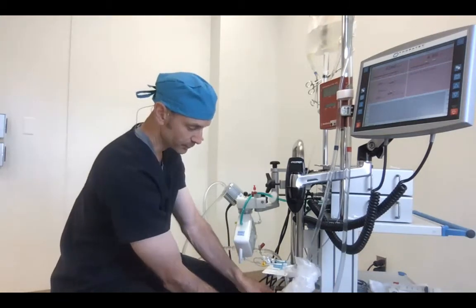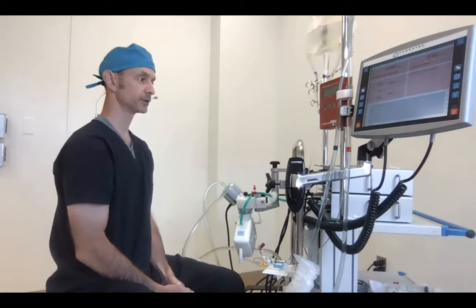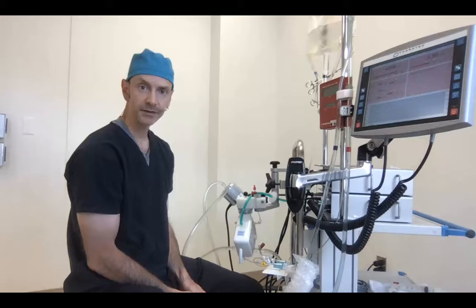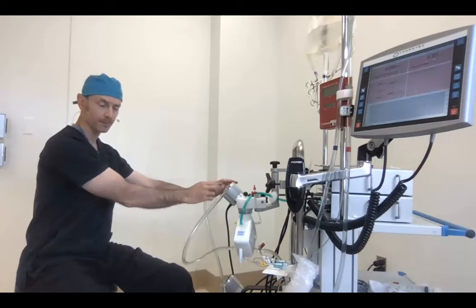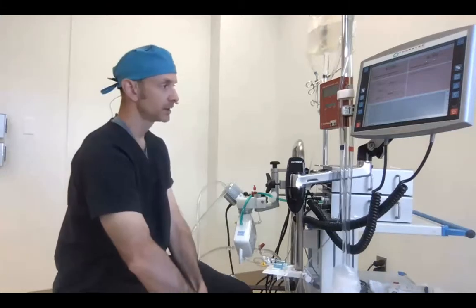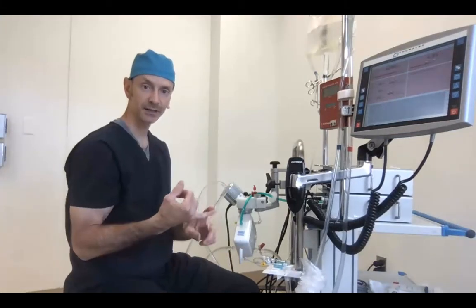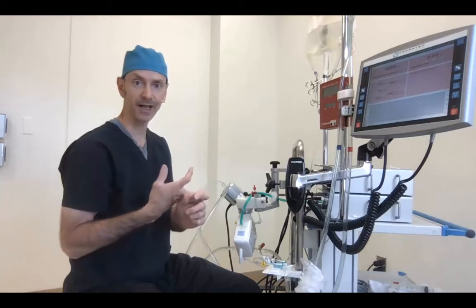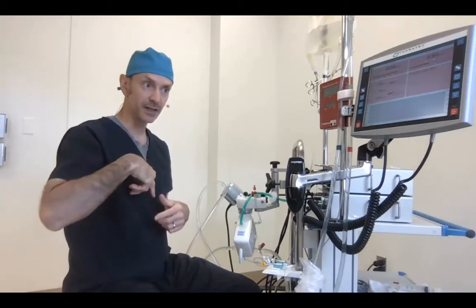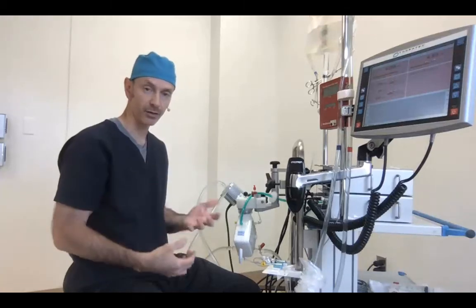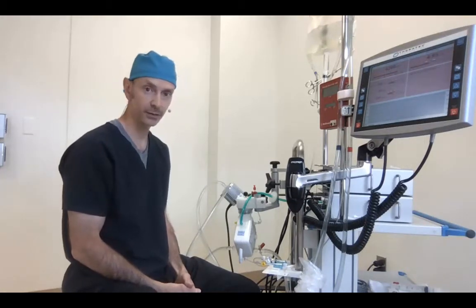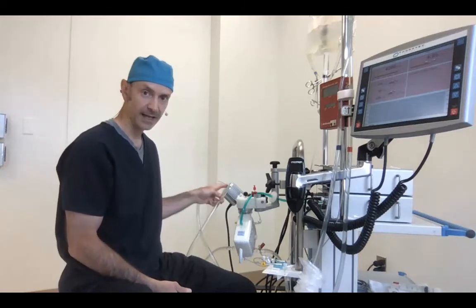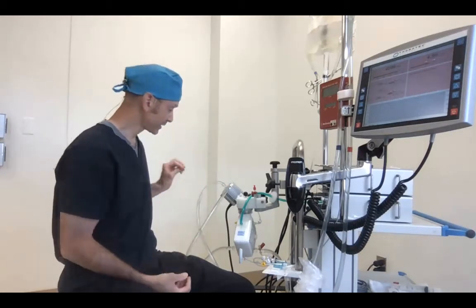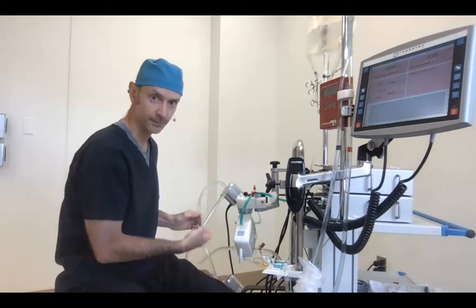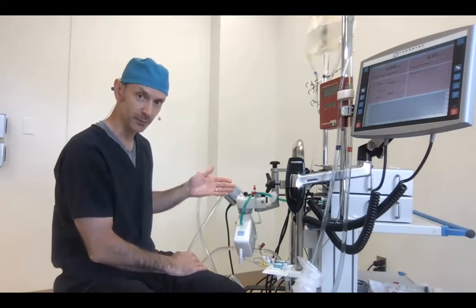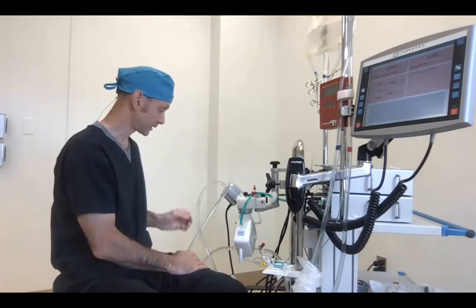But we're doing a demonstration of preload and afterload resistances. So what's preload? Preload is everything before this pump. So here's our pump, and this whole venous line up to the patient, the size of the cannula, the position of the cannula, the volume status of the patient, the position of the cannula inside the patient, the position of the patient on the bed. All these things factor into the preload. And this pump is preload dependent and afterload dependent. So just like the heart, if it has difficulty filling, that's the preload. If it has difficulty filling, then it has difficulty pumping.